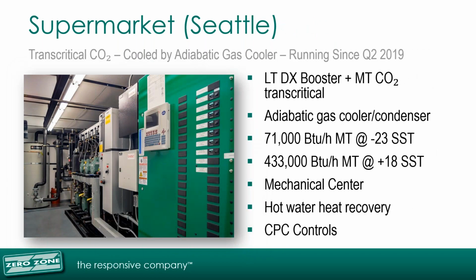On to transcritical applications. As I walk you through the next several installations, you'll notice there is not a one-size-fits-all package. You will find our refrigeration systems are designed to meet the needs of the retailer. We've used all of the major control system manufacturers. In this instance, we have a CO2 transcritical booster solution packaged within a mechanical center. The mechanical center included the hot water and heat reclaim system for the store. The mechanical center was set on the roof of the building. It's a nice compact package that simplified the installation for the contractor while saving the retailer space, time, and money.